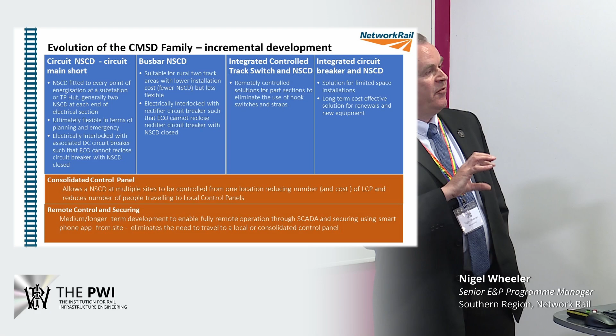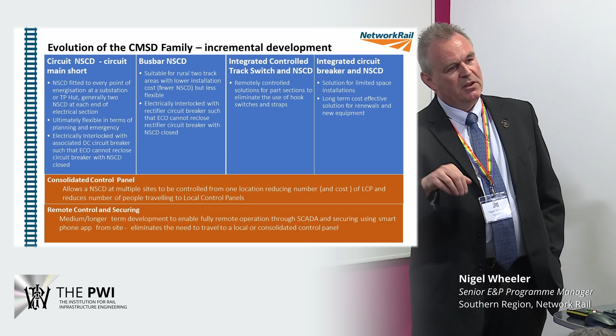We've also got consolidated control. Currently all the devices are operated through a local control panel, but they just operate for one substation or TP hut. We've now developed consolidated control where we can control 5, 6, 7 sites from one location, which means we don't need local control panels that could be a mile away from the substation. That makes it cheaper, and means we only need to send one person to site to operate the equipment.